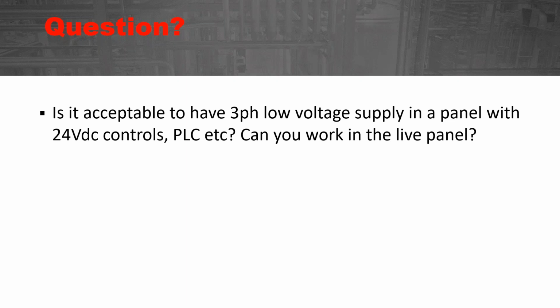And going back to the part where we're talking about working on this live, unless there's another problem, and this is going to come up later with energized work and the reasons why we can work on something energized, if it's less than 50 volt and there's no additional hazards, then we're going to be permitted to work on it energized. But kind of giving you an idea of what we're going to talk about when we get there, how close are you to the 208 volts?